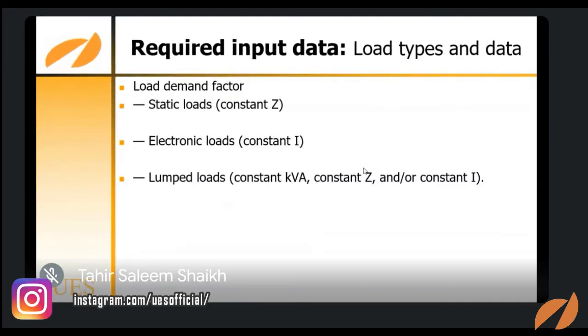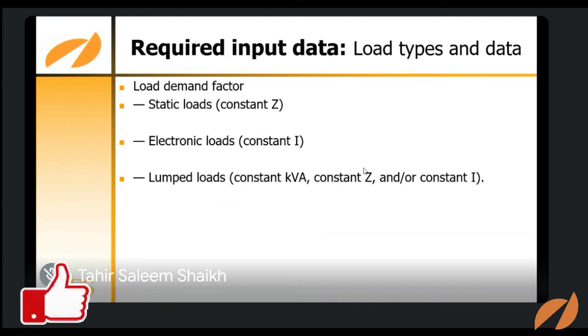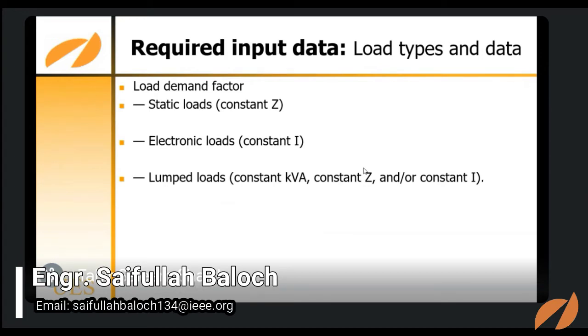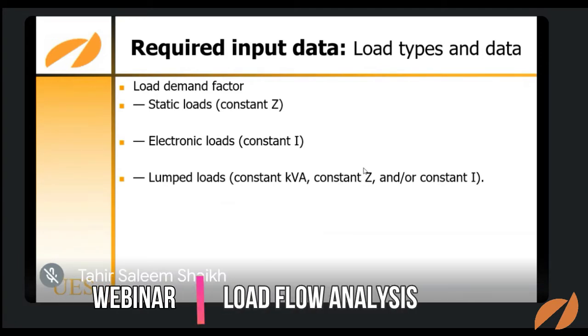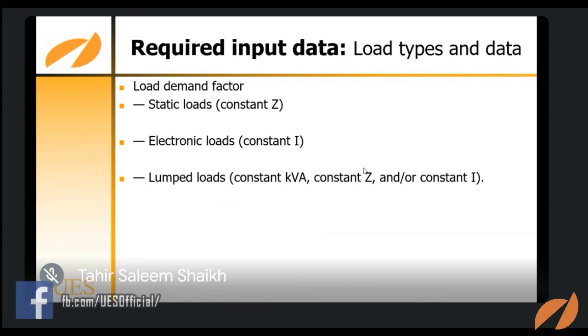Now load demand factor, static loads, electronic loads, lumped loads. Static loads are constant impedance loads. These are simple, very basic loads. Electronic loads are constant current loads. As you find in your surroundings, there are hundreds of electronics. These are called electronic loads. And a lumped load is itself a network of different connected loads.